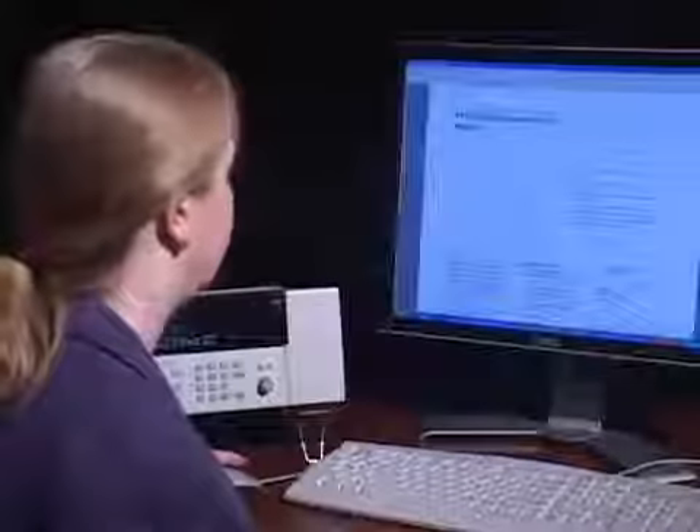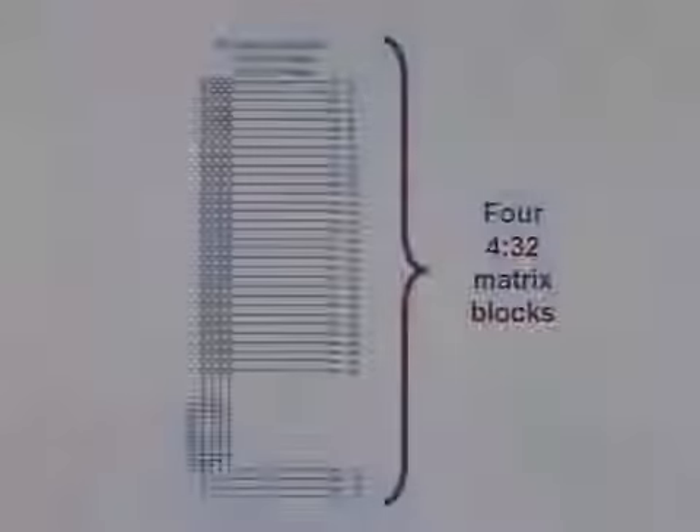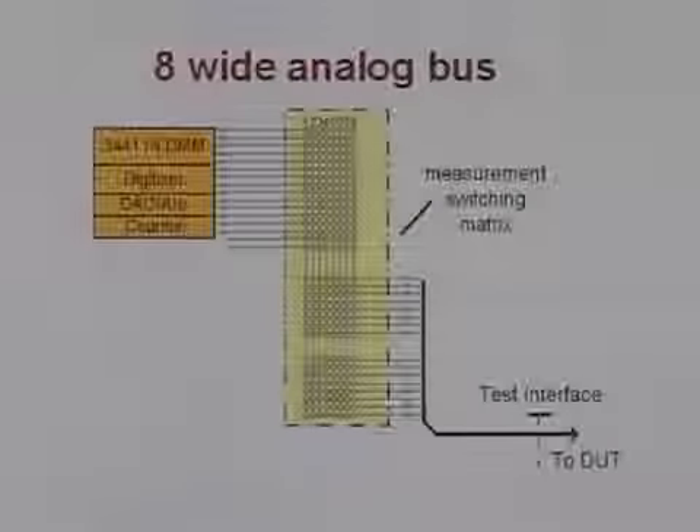Managing this high number of pins has just become easier with the new Agilent 34934A high density matrix module. The 34934A matrix module is organized as four blocks of four by 32, so multiple architectures can be configured, one of which will suit your needs.